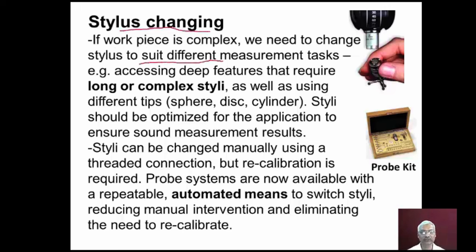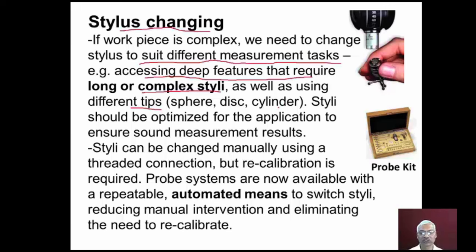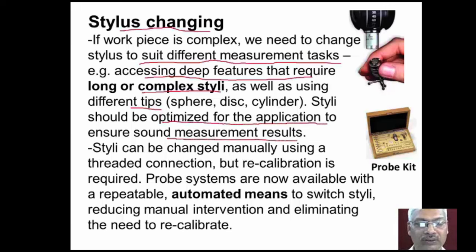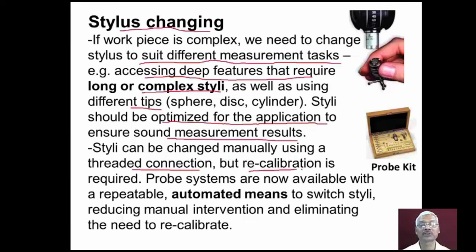Depending upon the inspection requirement, sometimes we need to change the stylus. If the workpiece is very complex, we need to change the stylus to suit different measurement tasks — for example, accessing deep features that require long and complex styluses, as well as using different tips like spherical, disc type, and cylindrical type for measurement of threads. Styluses should be optimized for the application to ensure sound measurement results. Styluses can be changed manually using a threaded connection, but whenever changed manually, recalibration is essential. Probe systems are now available with repeatable automated means to switch styluses, reducing manual intervention and eliminating the need to recalibrate.